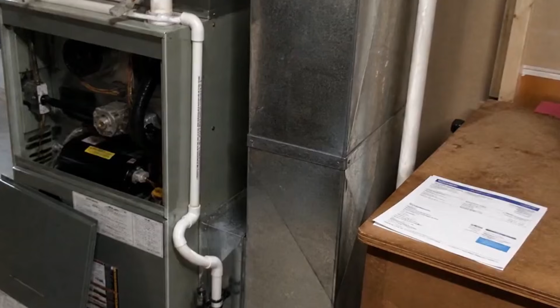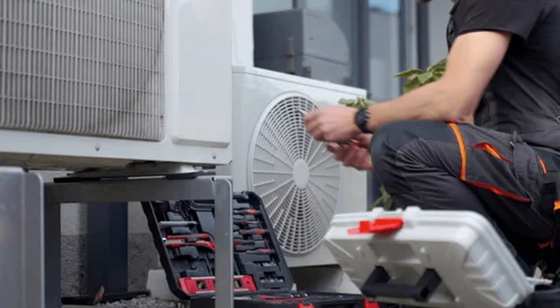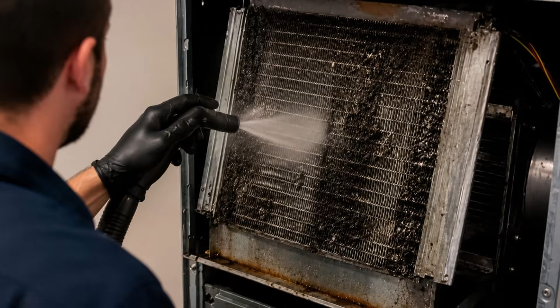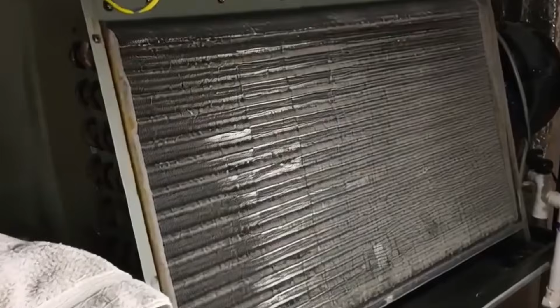4. The money they never bring up because it isn't a repair. Everyone talks about the service call. Nobody mentions what a dirty system costs you every single month it runs. That same biological film grows on your evaporator coil, the indoor coil your air blows across to get cold. Once it coats the fins, it works exactly like a blanket over a cold surface. Your air can't touch the cold metal. Heat transfer drops, and the system just runs longer and longer trying to hit the number on your thermostat.